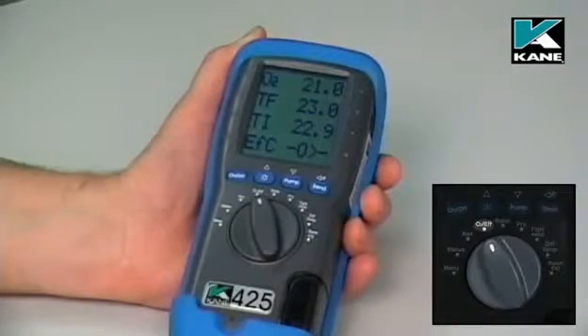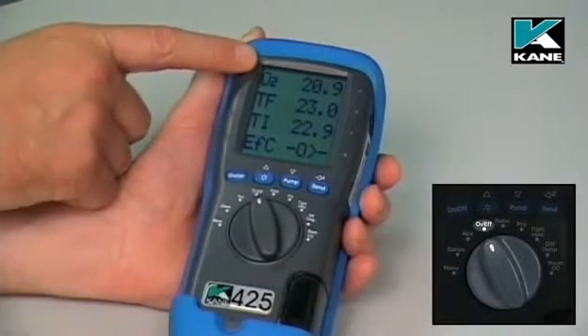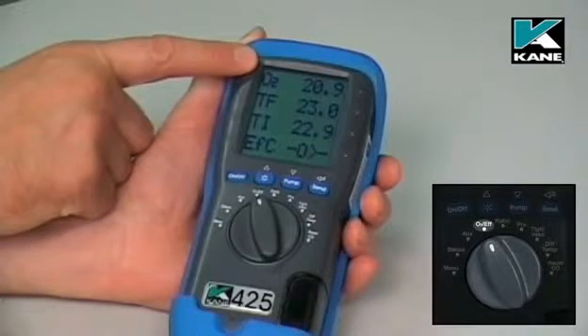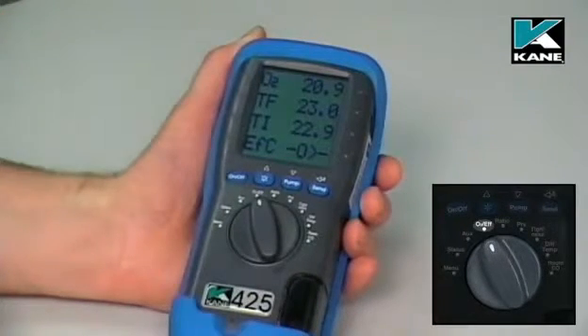Then move the dial to the oxygen and efficiency position. In fresh air, the oxygen reading should be 20.9%. Now that may vary by 0.1% either way, so either 20.8 or 21% is perfectly acceptable.